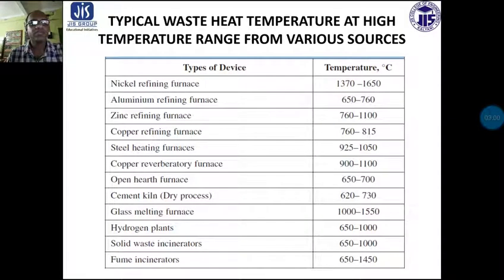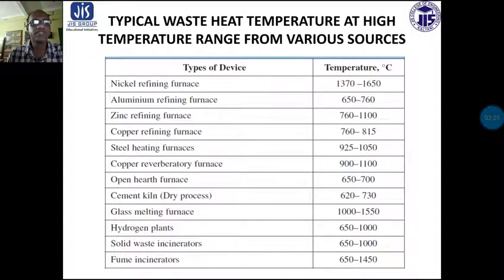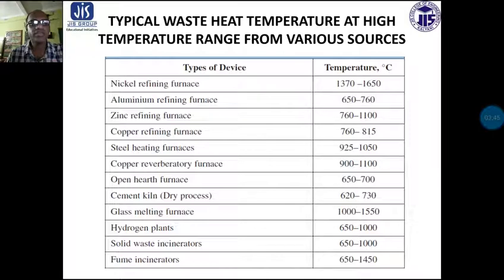There are some typical waste heat temperatures at high temperature range from various sources. Nickel refining furnace flue gas exits at 1370 to 1650 degree centigrade. Aluminum refining furnace is as high as 650 to 760 degree centigrade. Zinc refining furnace temperature ranges 760 to 1100 degree centigrade. Copper refining furnace is also 760 to 815 degree centigrade. Steel heating furnace 925 to 1050 degree centigrade. Copper reverberatory furnace 900 to 1100 degree centigrade.